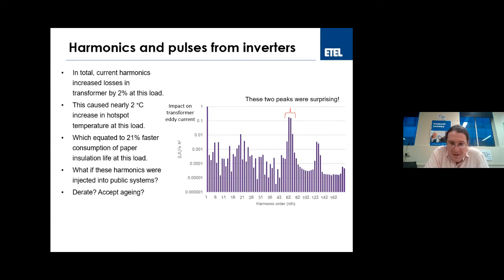Now, if we know that these harmonics are there, then we're fine, because we can do engineering calculations. We can see what's going on. Probably the easiest way to deal with this is to look at derating the transformer if there are harmonics on it. We can do that by calculation.